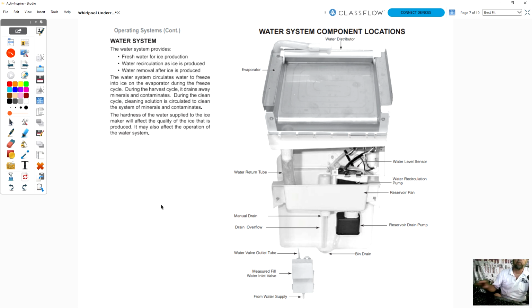It will build up mold and algae in your reservoir, and in the back behind this cover, you'll also find that buildup. I highly recommend, if you ever get a service call, that they do have a cleaning solution that can be put in the bin and recirculated so the internal components are clean. But you can remove this reservoir here with just these 2 wing nuts, and you can manually clean them out. So I would always recommend selling them a repair, but then offering them a discounted rate if they'd like you to clean it out.